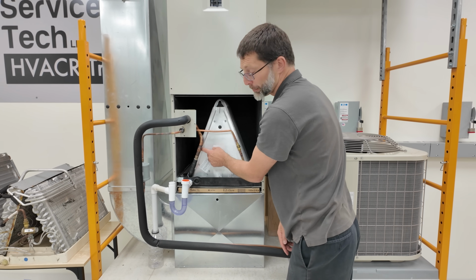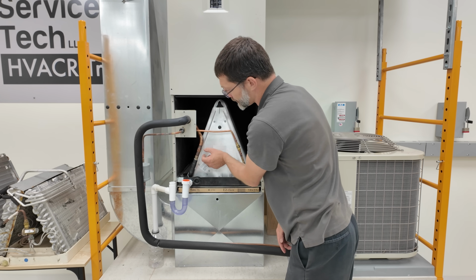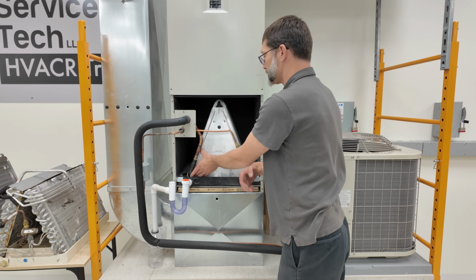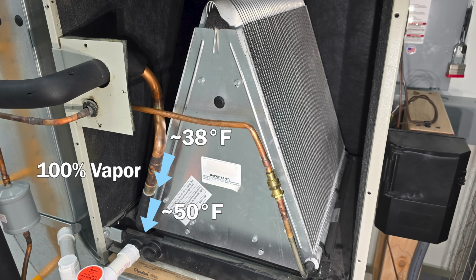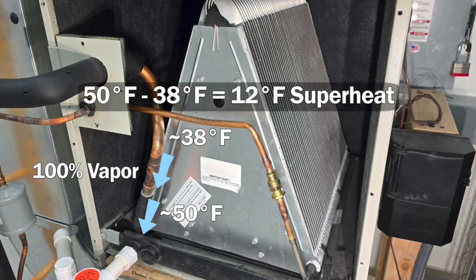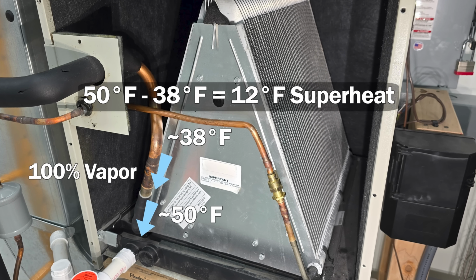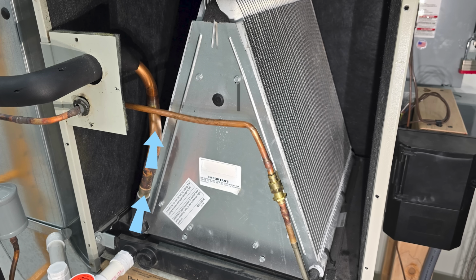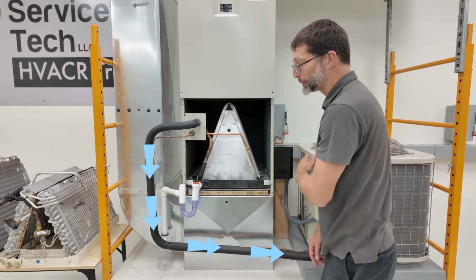Then it's going to change completely into a vapor state, and it's going to increase in temperature. Maybe it changes to, say, 50 degrees for the temperature of the vapor as it's exiting. So that'll be 12 degrees of superheat as it's then exiting and heading back over to that vapor compressor.